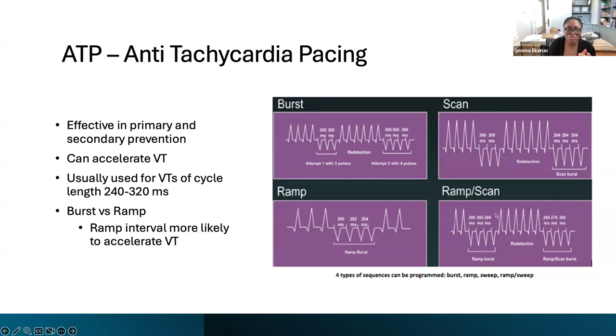And so you can do a burst, you can do a ramp, you can do a scan, and a scan just slowly increases the number. The idea is that while you're doing that, you're hoping you're able to convert. And then if you don't convert after a period, the device will say, okay, we've done this enough, we're going to shock now.